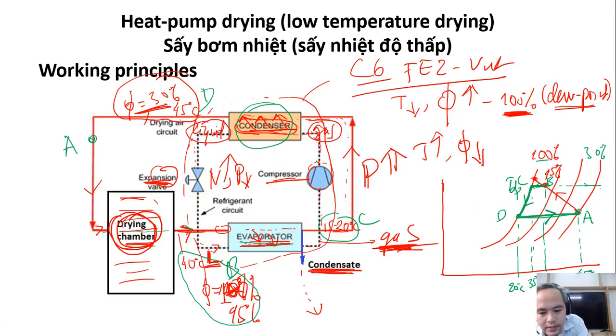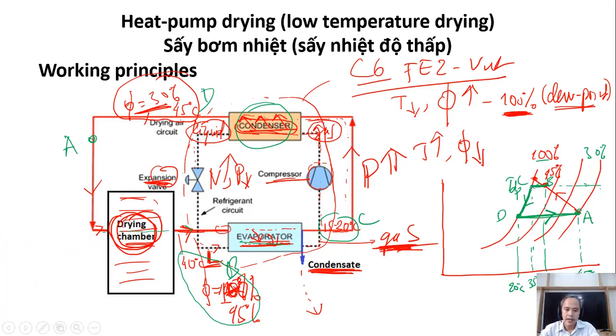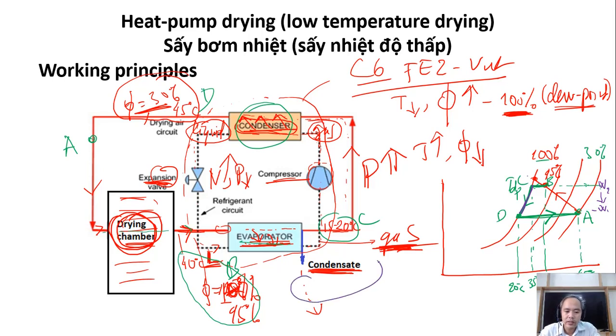From point C to point D, there is a drop in absolute humidity. This means part of the vapor has been removed from the air by condensation. When you remove this condensate, you lower the absolute humidity of the air. After that, you heat it up, which reduces the relative humidity, and the air can be used for drying again.